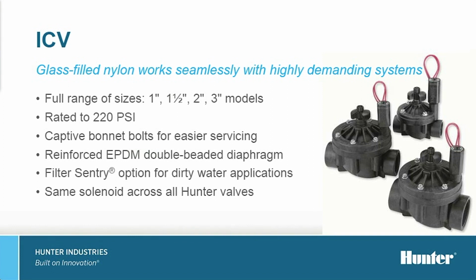Not only are the body and bonnet super strong, but so is the diaphragm. The diaphragm is made from a fabric reinforced EPDM to prevent tearing, and the double beaded design creates a better seal between the body and the bonnet. The filter sentry option has a scraper attached to the diaphragm filter, moving up and down on the filter as water flows through the diaphragm, keeping the diaphragm clean and functional in dirty water conditions. The filter sentry feature is attached to the diaphragm, so this can be added later in the field if needed.